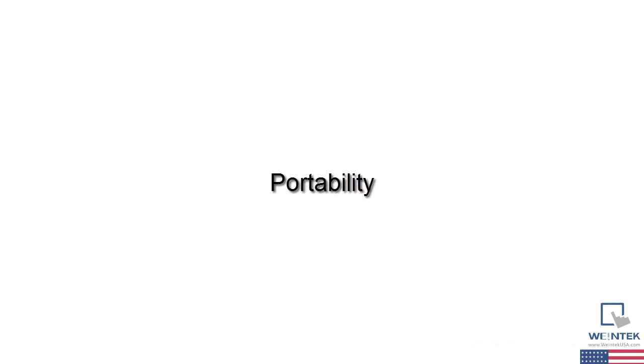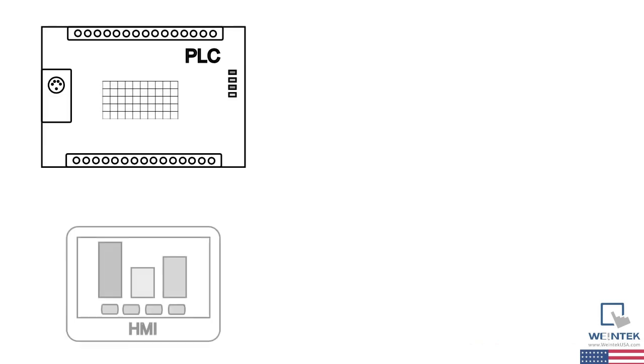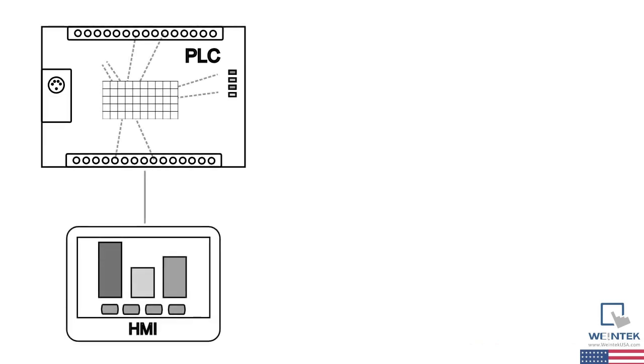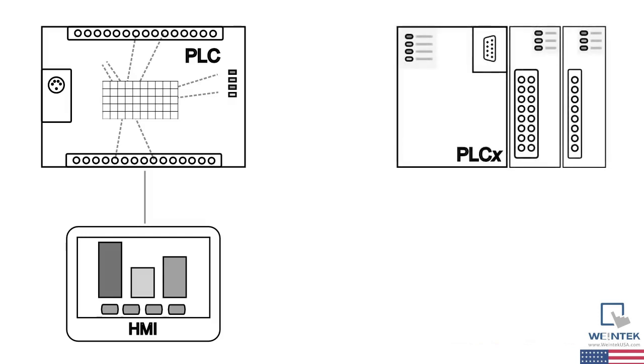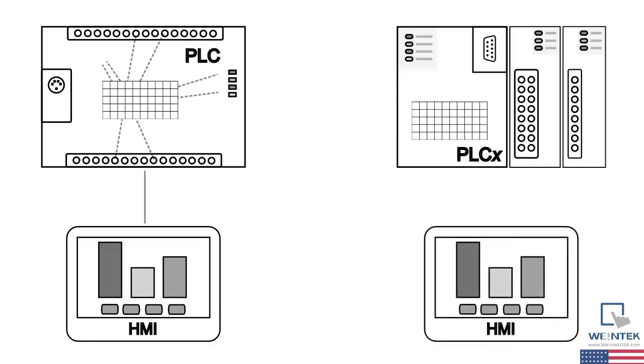Finally, the approach we are advocating here will make your designs more portable, which is to say reusable. This comes into play if you want to reuse your code with new hardware. Using a well-designed interface between the HMI and PLC, as we've been discussing, decouples to some degree the PLC and HMI configurations, allowing a more standardized approach that is less dependent on the peculiarities of the particular hardware, making it easier to upgrade to new models or brands, as is often required by cost, changing company policies, or obsolescence.